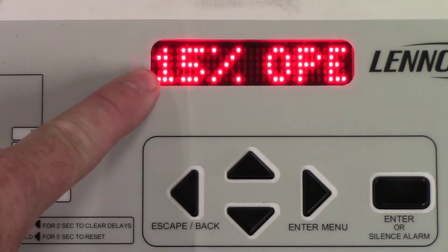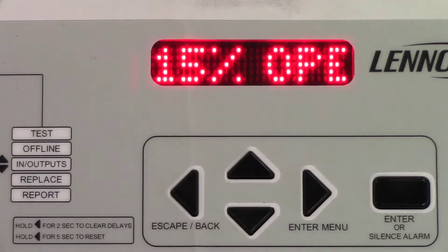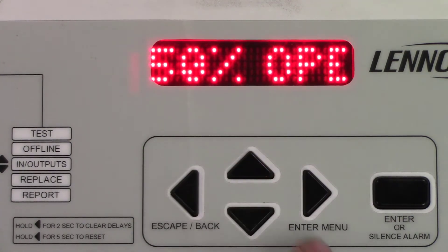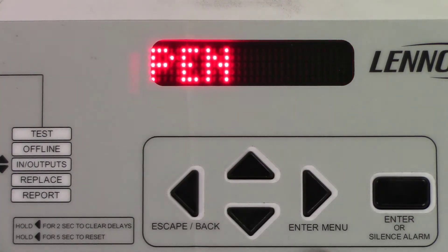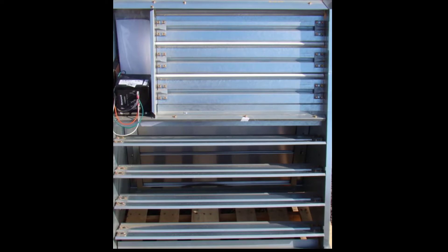You can see that it shows 15% open. If you press the up or down arrow it adjusts the economizer. Run the economizer to 100% open and check to see if it's open the whole way. Then run the economizer to 50% open and make sure that it's open halfway.